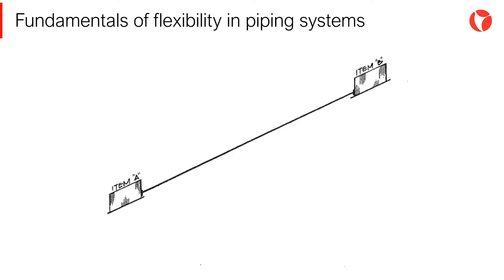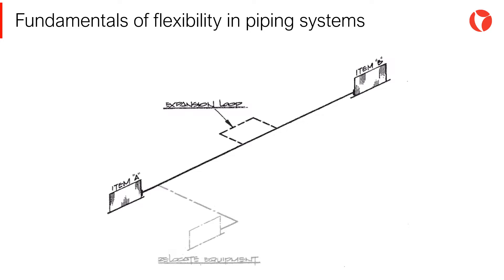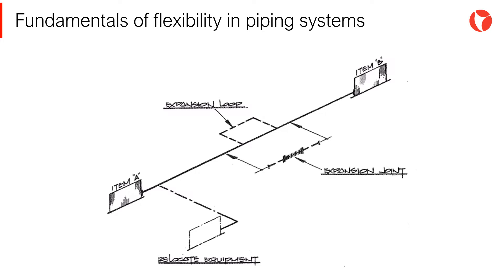As seen in the picture on the screen, the most direct way to connect items A and B would be a straight pipe. Obviously, this way the system would be completely rigid. There are basically two ways to provide flexibility to a piping system: by introducing changes in direction of the system, as a spatial loop, or moving one of the items to be connected. The alternative is to install expansion joints.